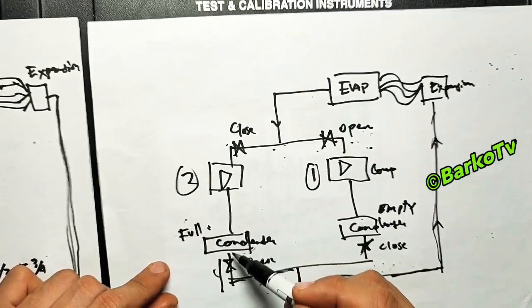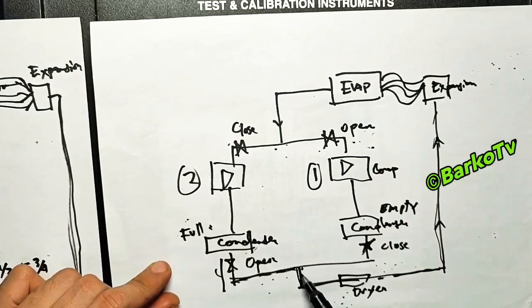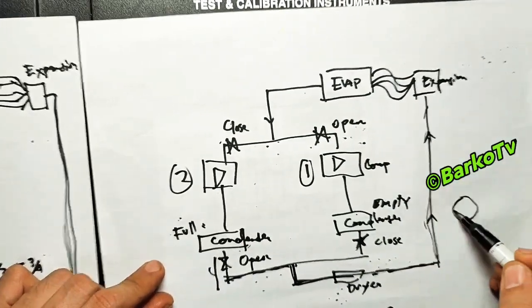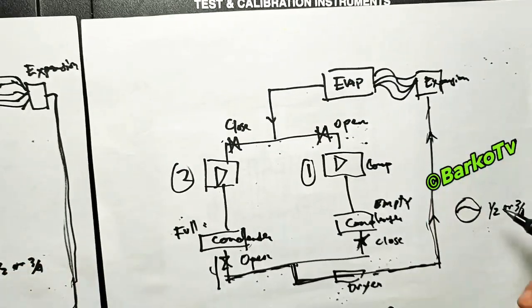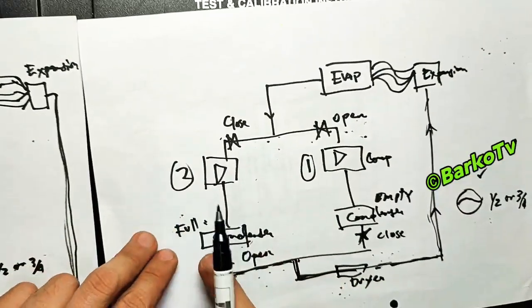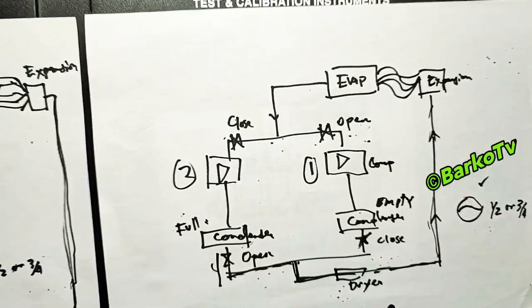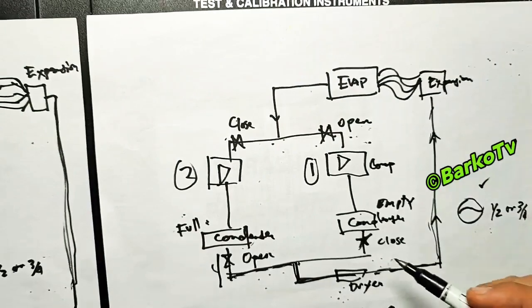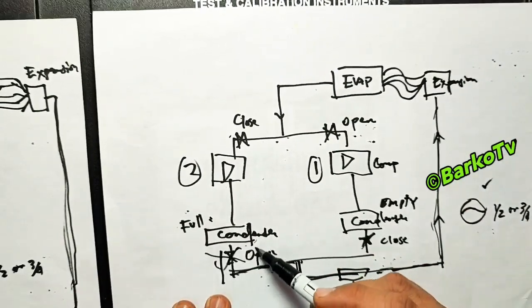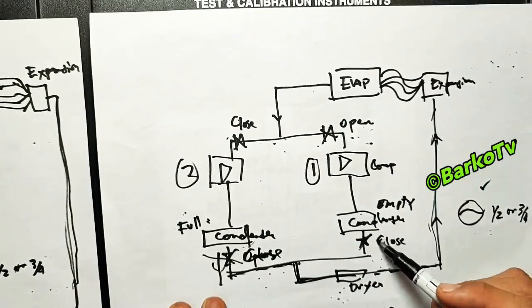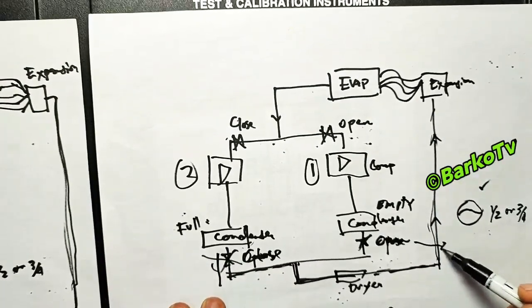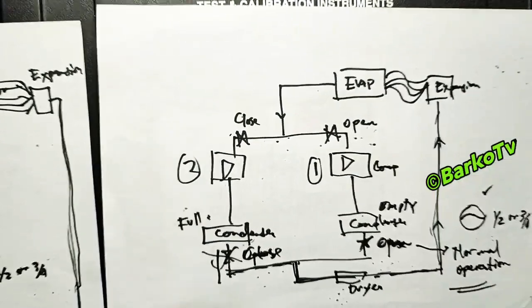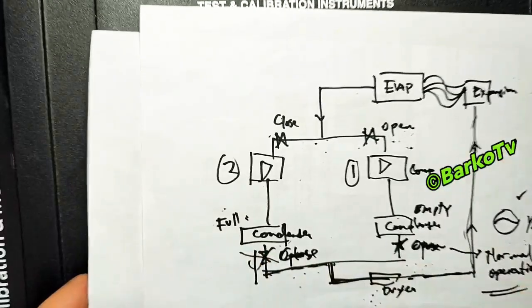The scenario is: we need to transfer the refrigerant of number 2 going to number 1. The condenser after-condenser valve of number 2 is open - the pressure goes to the dryer, to expansion valve, evaporator, and suction, which is suctioned by compressor number 1 and stored in the number 1 condenser. You need to stop when the level reaches one half or three fourths to be safe. After reaching that level, close the number 2 condenser and open the after-condenser for number 1 so that you can operate at normal operation. You will have a closed loop for number 1.